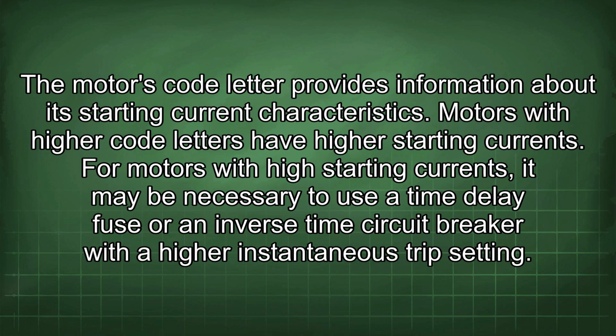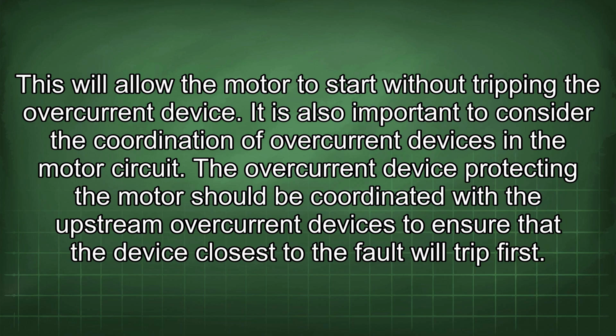The motor's code letter provides information about its starting current characteristics. Motors with higher code letters have higher starting currents. For motors with high starting currents, it may be necessary to use a time delay fuse or an inverse time circuit breaker with a higher instantaneous trip setting. This will allow the motor to start without tripping the overcurrent device.